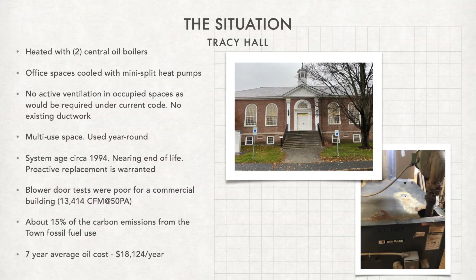As we were talking about this, EEI pointed out that the building is not up to current code. It's grandfathered for not having active central ventilation and cooling. If we were to do anything but just replace the oil boilers, we will need to install ventilation and cooling. It already has a little cooling, but it's not up to code. So the project just got twice as big as soon as we realized that. And since the agenda of the whole thing is to get rid of fossil fuels, we're basically going to have to tackle that problem.